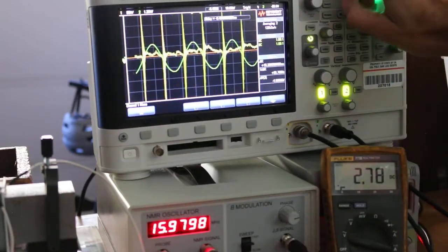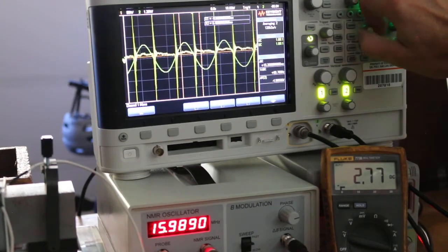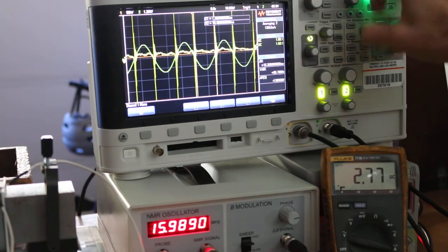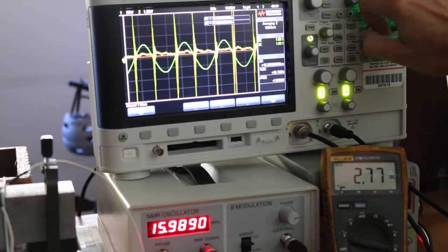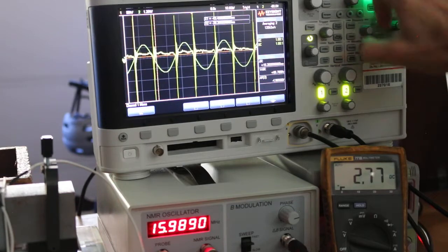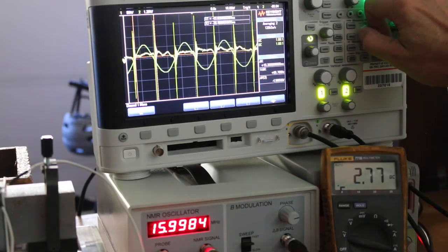Now I'm going to go over here, oops, wrong button. See, these two are about the same width too, the same spacing apart. These two are about the same spacing apart, and these two look okay too. The only reason I'm judging this is that as I sweep to the resonances, both of them are lining up with these dotted vertical cursor lines. These aren't so well aligned, but now if I go back to the original, those have drifted as well. They're not as aligned as they were, so I'm going to go back and tweak the frequency, going a little bit lower here to make them all line up again.